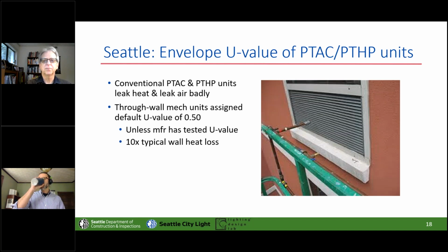PTACs and PTHPs, package terminal air conditioner or heat pump. They become part of the wall assembly. You've seen these in all the cheap motels you've stayed in over the years, the ones that roar to life when they start running and then stop. They tend to have a U-value as opposed to the 0.056 or something, they tend to have an insulating value of 0.5, so something on the order of 10 times more heat loss through them. Even though this is a mechanical talk today, just be aware that our envelope requirements now require you to recognize and make up for the fact that you have a dramatically different amount of heat loss through those units.